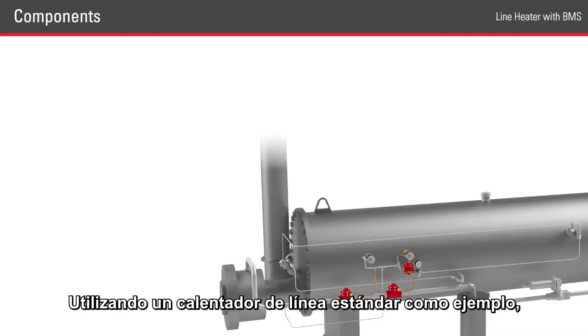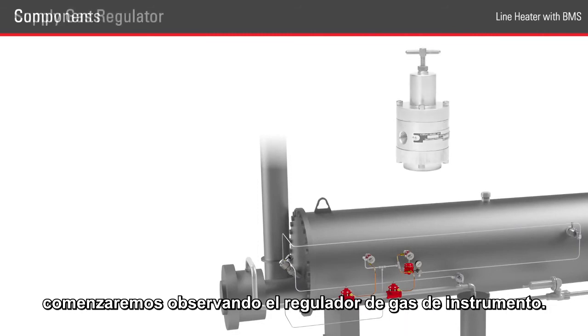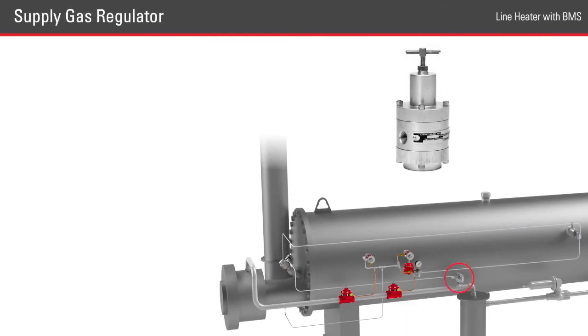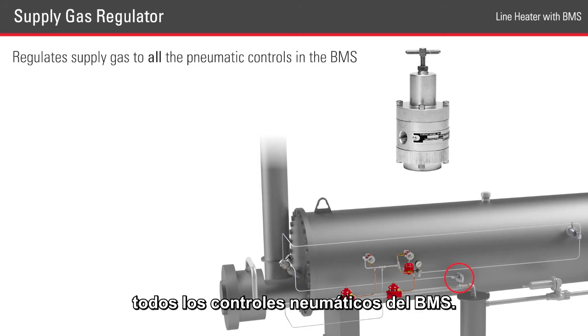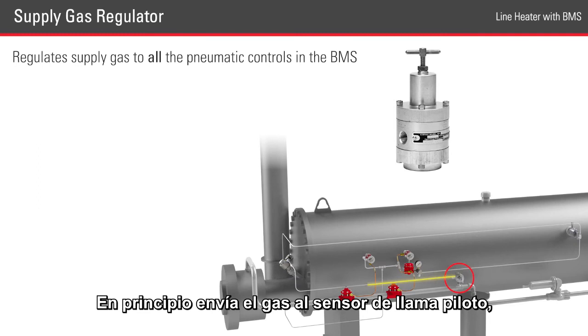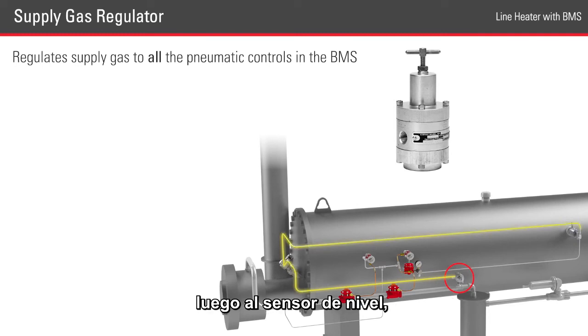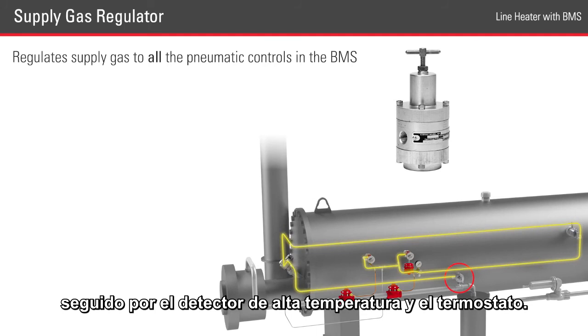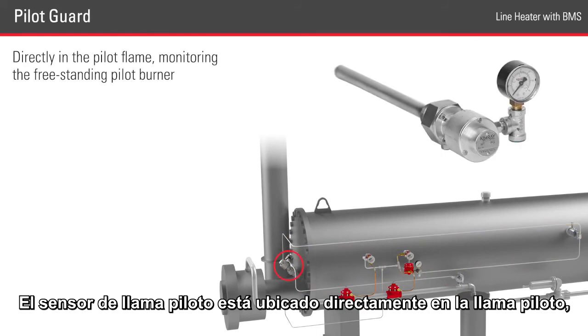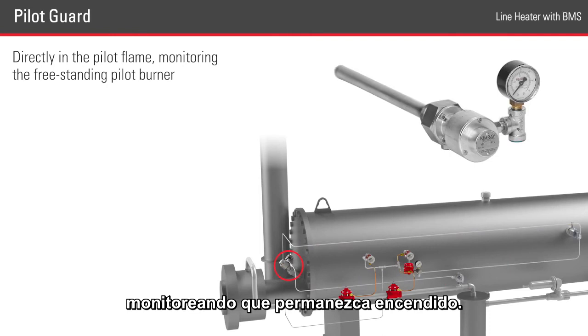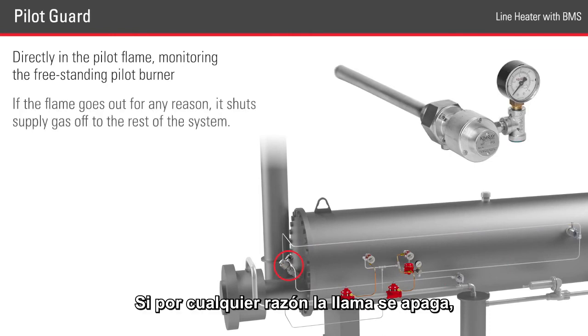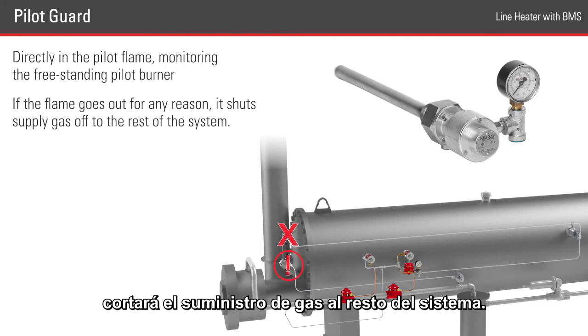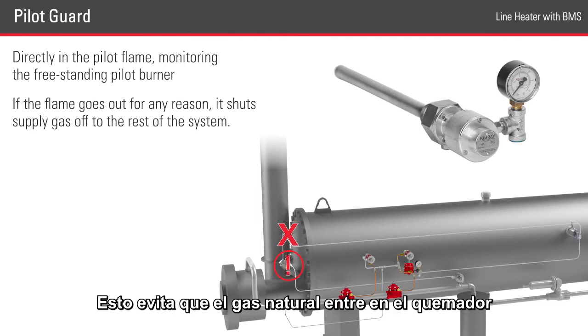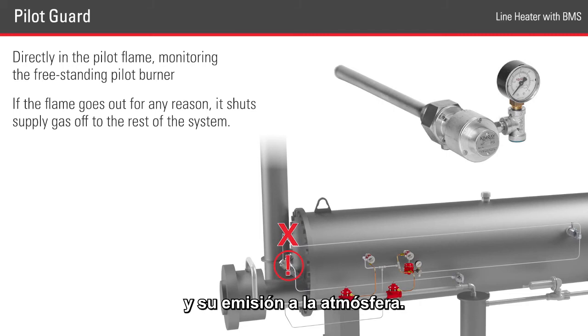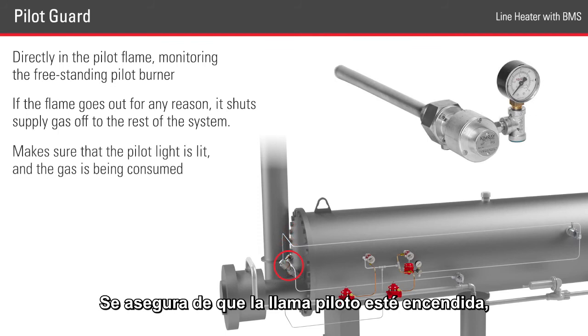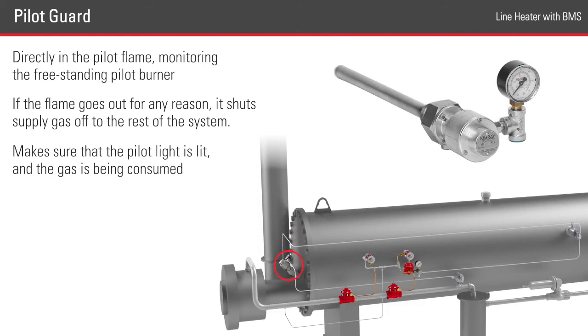Using a standard line heater as an example, we'll start by looking at the supply gas regulator. This regulator supplies gas to all the pneumatic controls in the BMS. It initially leads to the pilot guard, which then feeds the level switch, followed by a high temperature shutdown and thermostat. The pilot guard is directly in the pilot flame, monitoring the freestanding pilot burner. If the flame goes out for any reason, it shuts the supply gas off to the rest of the system. This prevents natural gas from going into the burner without a pilot flame and being emitted into the atmosphere. It makes sure that the pilot light is lit and that the gas is being consumed.